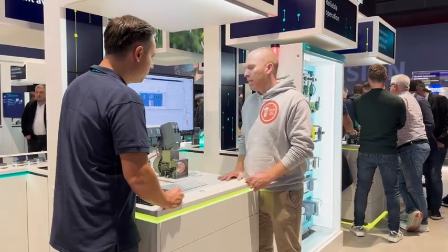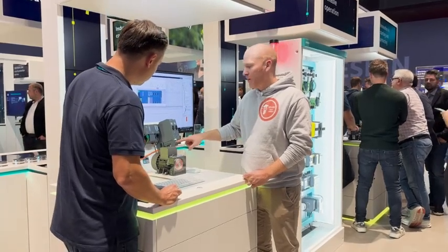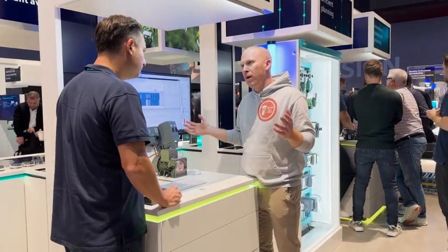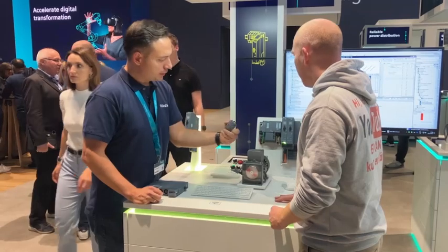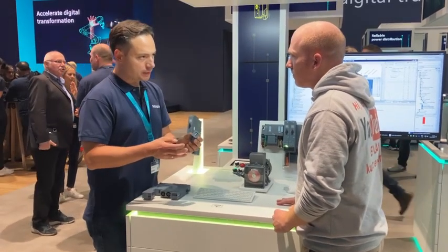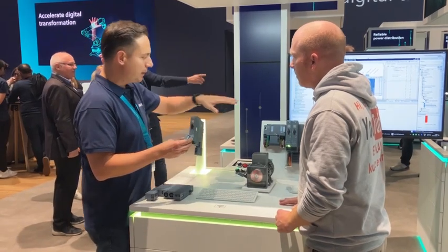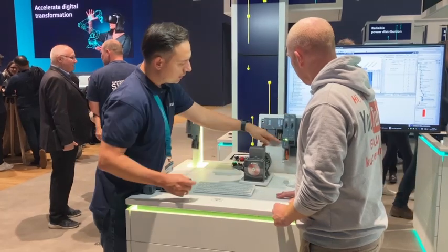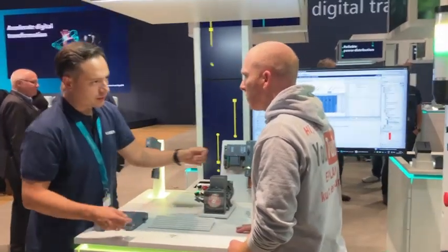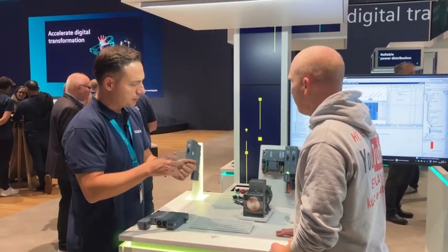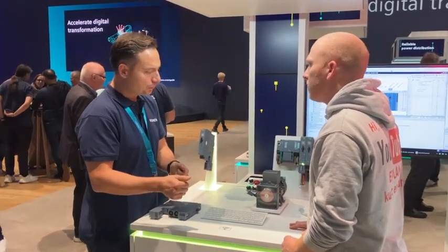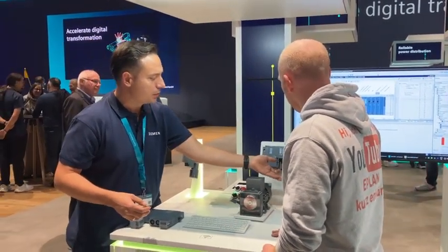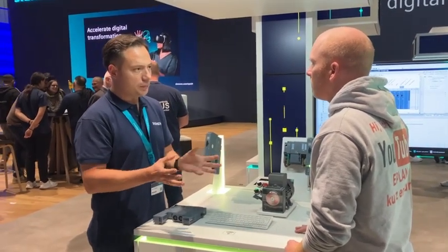right? Exactly. You have here also a small add-on, let's say, on the lower part here with some DIs. This can also be used to integrate, for example, a reset button. Exactly. So this is a module for local control. If you, for example, during commissioning want to test the application before the PLC is even running, then you can plug this into the e-starter and wire to these terminals here starting commands, for example, start the motor right, start the motor left, or stop. And then you can test if everything has been wired correctly.